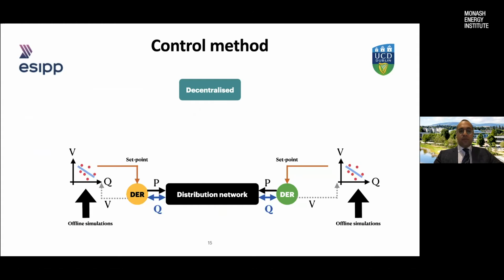First, we did some offline simulation and tuned every volt-var curve individually for each DER in the system. Then each DER, by sensing the voltage at its connection point, understands how much reactive power it should inject or absorb from the grid.